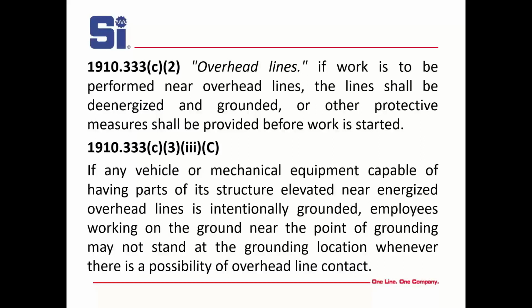So often what we have is static discharge, especially when you get into medium voltage, which is what this section considers. If any vehicle or mechanical equipment capable of having parts of its structure elevated, like a lift truck or something of that nature, near energized overhead lines is intentionally grounded, employees working on the ground near the point of grounding may not stand at the grounding location. And we're going to talk about different ways to be near personal protective grounding locations.